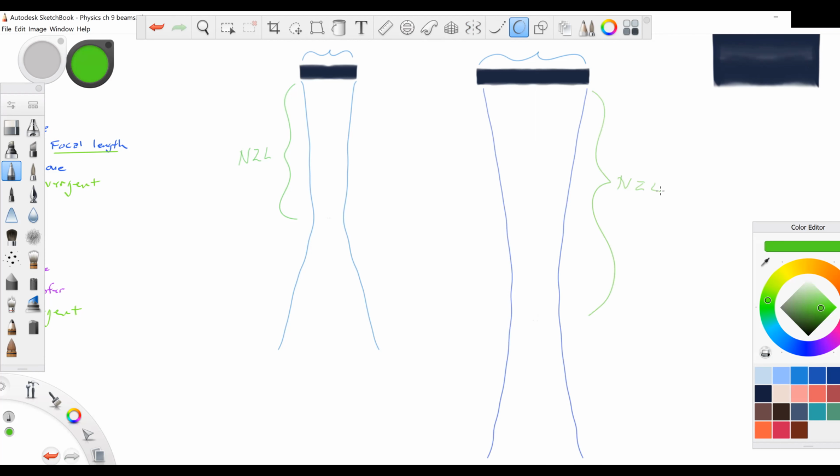So graphically, all I'm showing you here is that if you have a relatively small transducer diameter, so your element diameter is relatively small, that forces the focus or the near zone length to be a little closer to the transducer itself. A wider transducer or wider element will force the natural focus to be a little farther away. So that's one thing to think about.